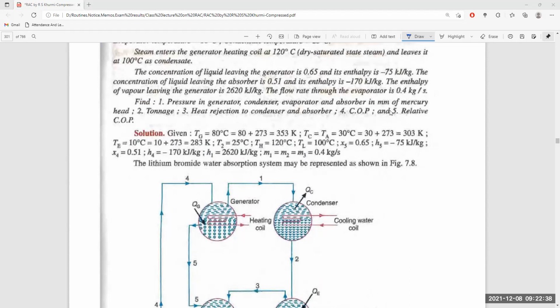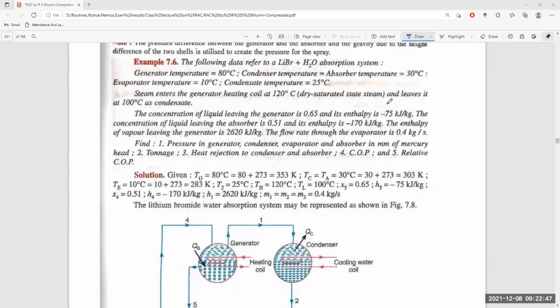For the evaporator, 10 degrees centigrade, 10 plus 273, and T2, that is 25 degrees centigrade condensate temperature, and TH, the high temperature, is 120 degrees centigrade. Steam enters the generator heating coil at 120 degrees centigrade, and T leaving is 100 degrees centigrade.